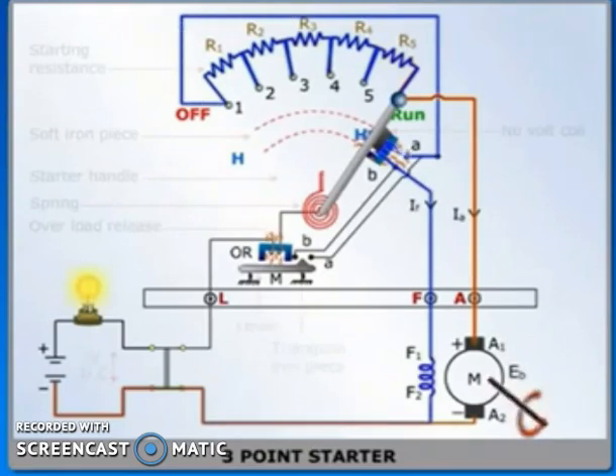With this arrangement, the starting resistance in the armature circuit can either be zero or full. The handle can be left on any intermediate stud willingly or unwillingly. The field winding, hold coil HC, and the starting resistance are in series. Since the starting resistance is much smaller in comparison with the shunt field resistance, its effect on the shunt field current is negligible.